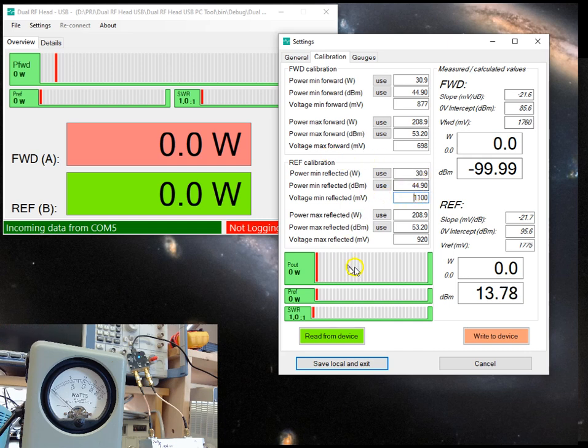That's all that is needed for the calibration. One thing I should emphasize is that the easier approach is to enter the value in the watt field and press use, which will calculate the dBm value. Actually, the dBm values are what is configured in the device, everything in the device runs on dBm.